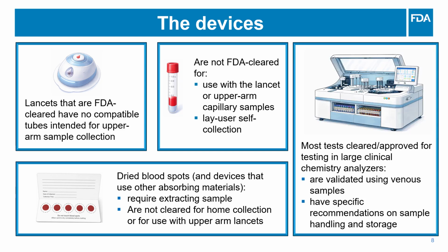Most tests that are cleared or approved for testing in large clinical chemistry analyzers have been validated using samples collected from a vein, and also have specific recommendations on sample handling and storage in their labeling. Sample collection devices need to align their instructions and handling conditions with the current labeled conditions of the test. Further, because the test manufacturers did not design their device for capillary blood nor for blood reconstituted from filtered paper, the design control processes and their quality systems do not address nor control for this mode of testing. Ensuring who assumes the regulatory responsibilities, including medical device reporting, recalls, design controls, for each piece of this ecosystem is vital to ensure safety and effective use of all these devices.